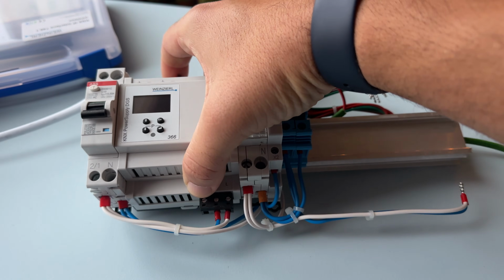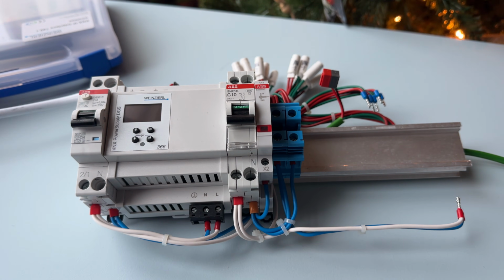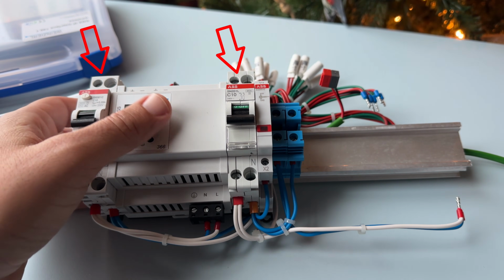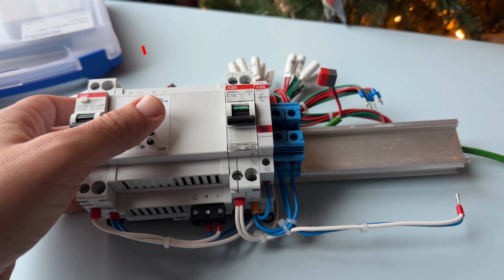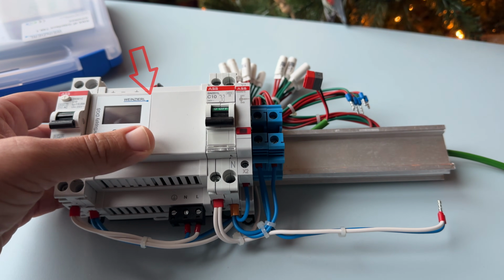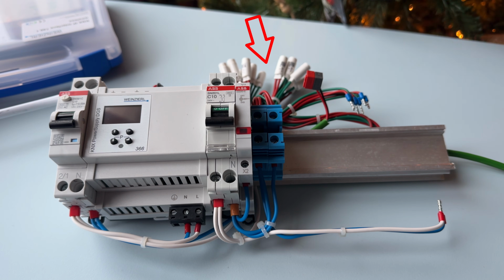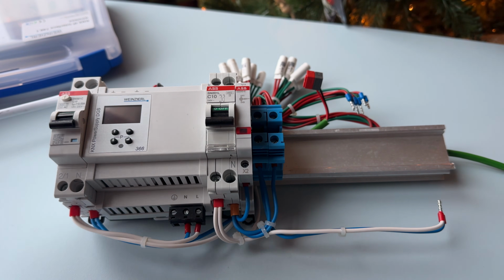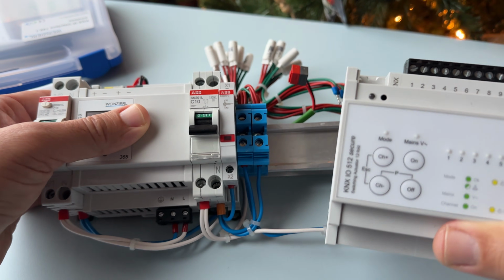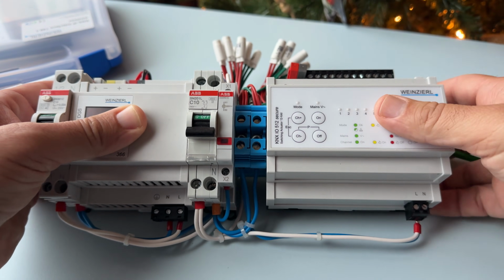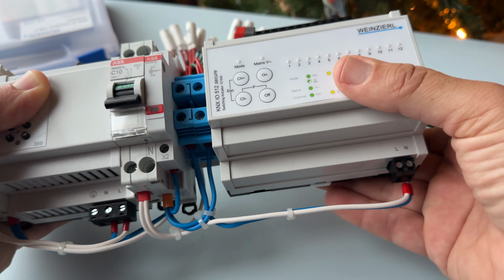For this demo, I'm using this DIN rail where I've already installed the necessary circuit breakers, a KNX power supply, and LEDs that I'll use as loads for the switching actuator. I'll now mount the KNX IO 512 on the DIN rail. It requires 6 DIN rail units.